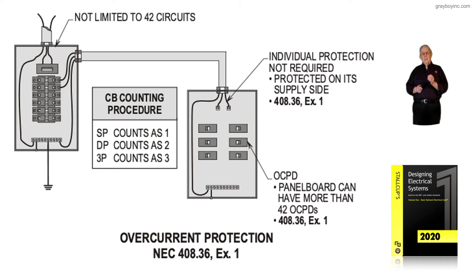So what does Figure 7-15 illustrate to the electrician or the designer? How do we count the number of overcurrent devices in the panel board as shown in the boxed-in information? And if we're locating that subpanel to the right in the same building or structure, then Article 215 is used.